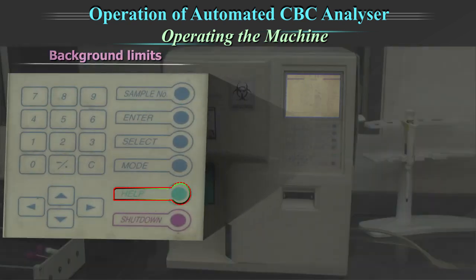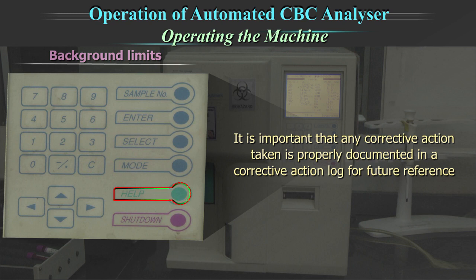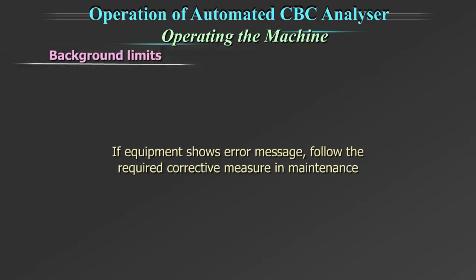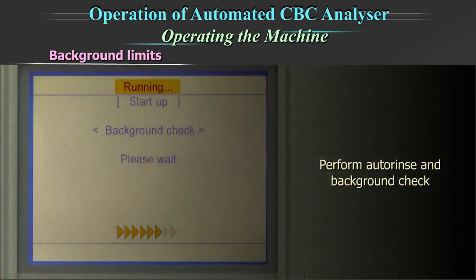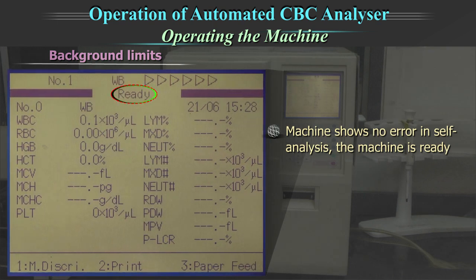At this stage, please go through the help menu and take corrective action as displayed. It is important that any corrective action taken is properly documented in a corrective action log for future reference. In case the equipment shows an error message, follow the required corrective measure in maintenance and perform auto rinse and background check. If the machine shows no error in self-analysis, the machine is ready for analysis.